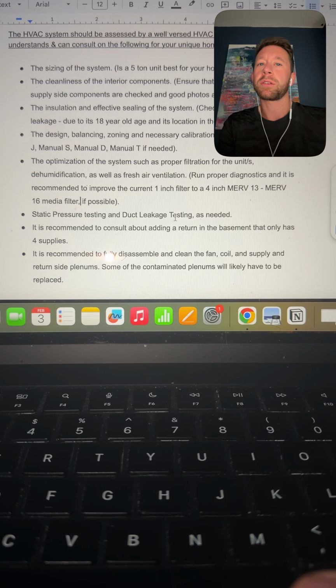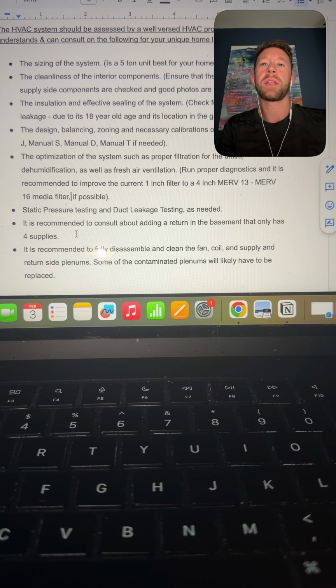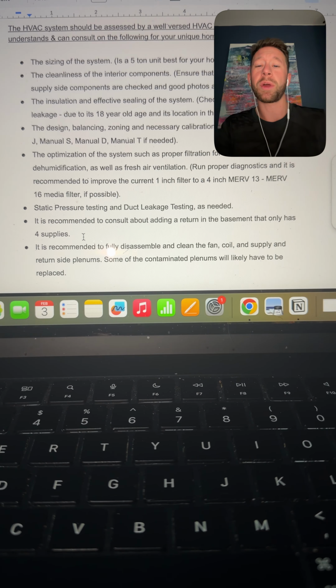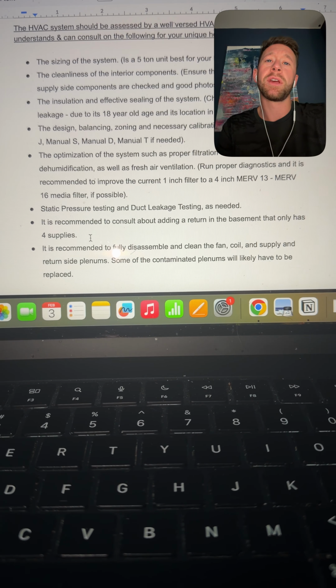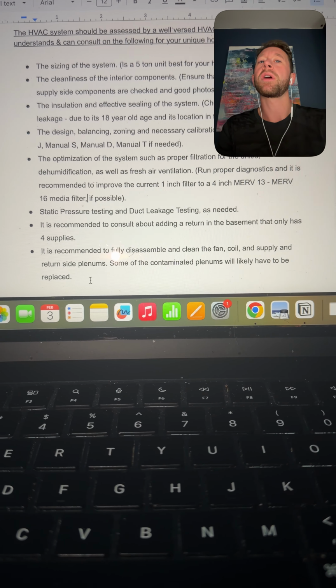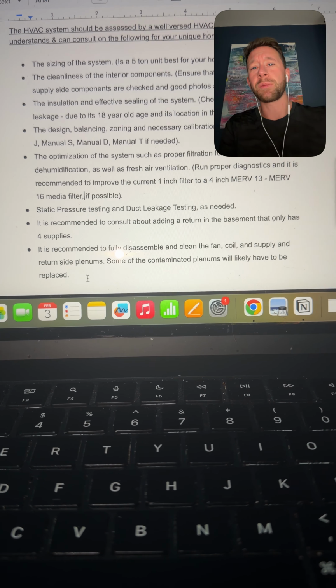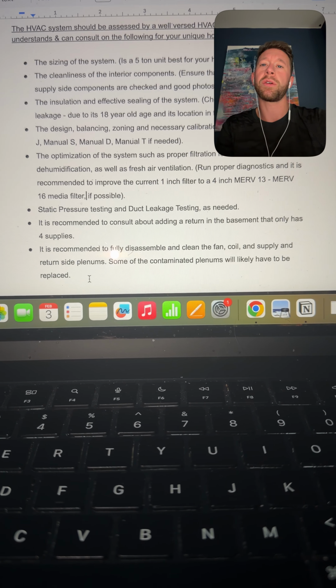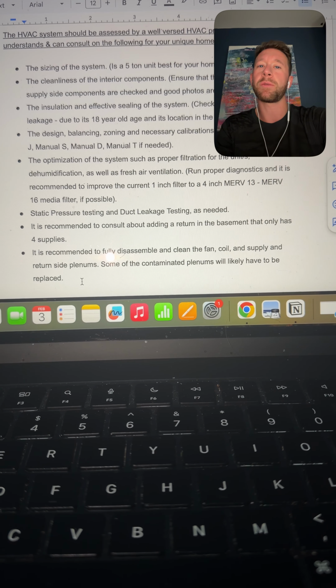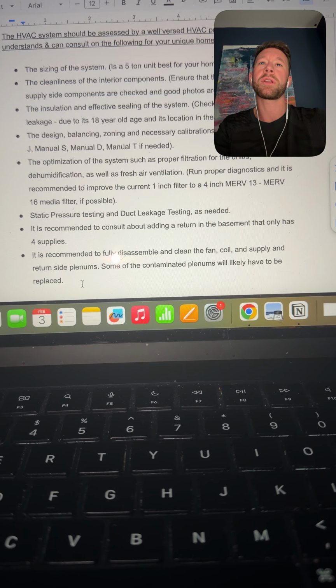Static pressure testing, duct leakage testing as needed if possible, and then it is recommended to talk with them about adding that return vent to the basement, and recommended to fully disassemble and clean the system, the fan, coil, and supply and return sides. Some of these contaminated plenums will likely have to be replaced.